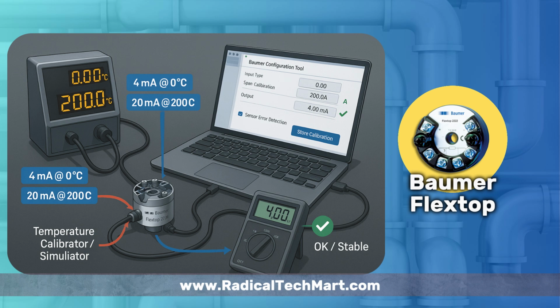For calibration, connect the RTD to a temperature source or simulator. At 0 degrees Celsius, verify the output is around 4 mA, and at 200 degrees Celsius, it should read close to 20 mA. If there's a small offset, use the zero and span calibration options inside the software to fine-tune the signal. Once stable, click Store Calibration to lock the settings.